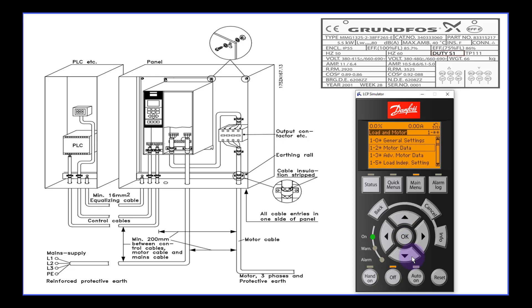Press the down arrow key to select 'motor data,' then press the OK button. The first thing to configure is the motor power — this is the motor power, 5.5 kW. Press the OK button to edit, then press the left or right arrow key to change the value. Change it to 5.5 kW, then press the OK button.